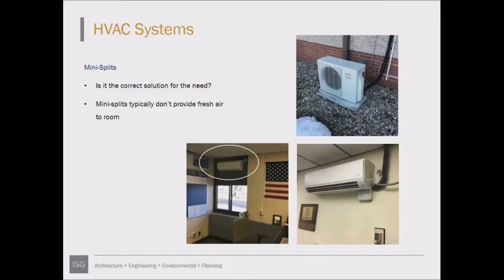Mini splits, we see this a lot these days where mini splits get put in and everyone thinks they've solved the problem. We've brought air conditioning into the space, true, but I haven't seen a mini split yet that's bringing in fresh air. Some might, some hybrid of this, but it does cool down the room. Believe it or not, one of these was where the univent was boarded off, so absolutely no fresh air. They are getting air conditioning. They're great for head end rooms to keep your IT equipment cool, but for general classrooms, you're not getting your ASHRAE standard air rates into the rooms.